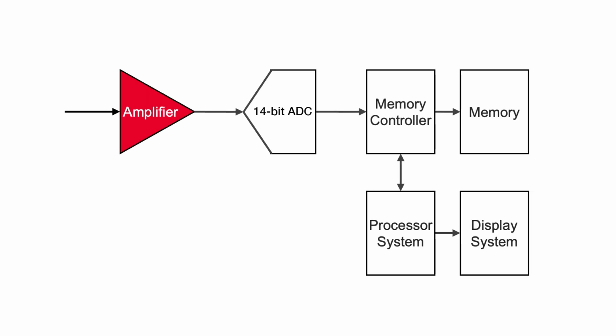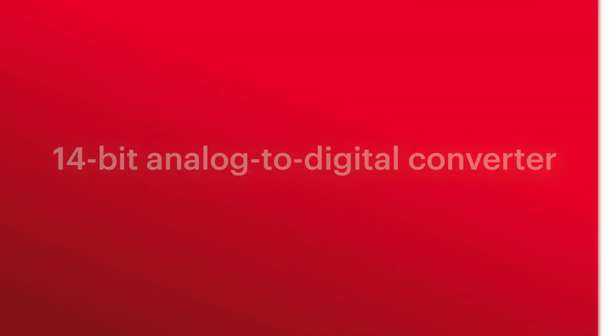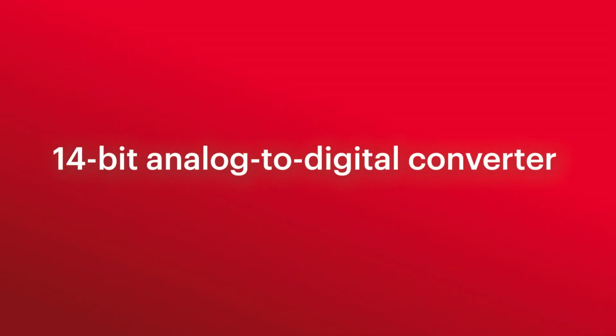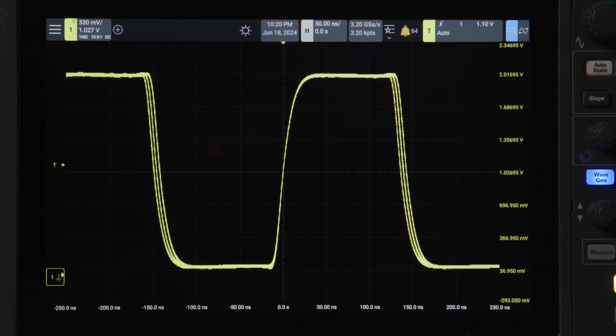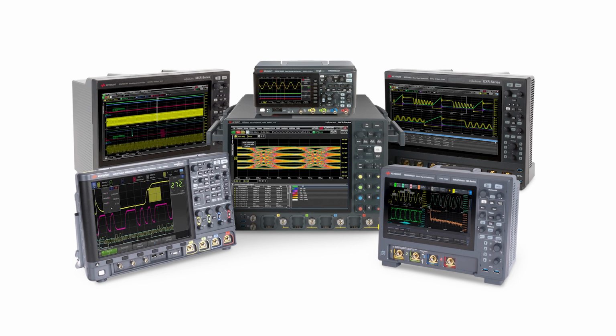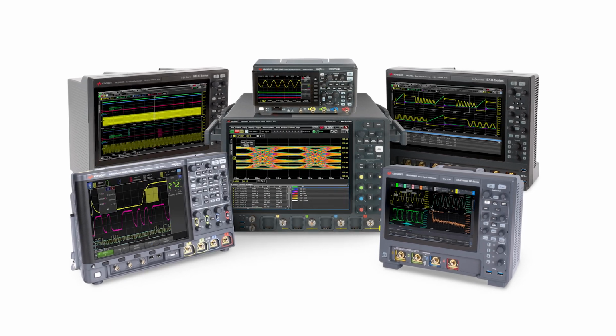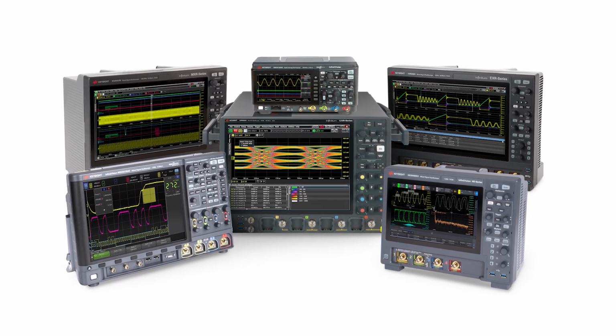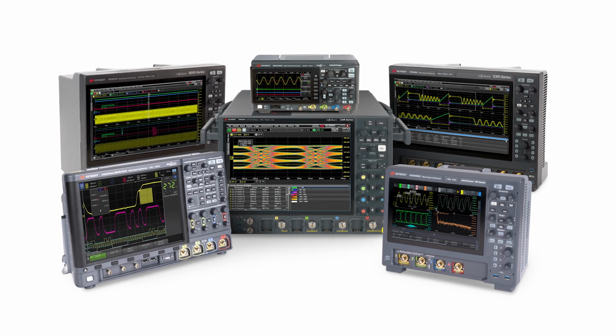The primary reason to push the noise and signal integrity capability of the oscilloscope to the limits is to take full advantage of the new 14-bit ADC, and the new ADC and memory controller systems are a result of years of developing high-performance ADCs to accurately recreate the sampled waveform. The team maintained the fastest, uncompromised waveform update rate of previous products and combined it with the technology used in our higher bandwidth products to produce the signal fidelity and measurement capability of this oscilloscope.